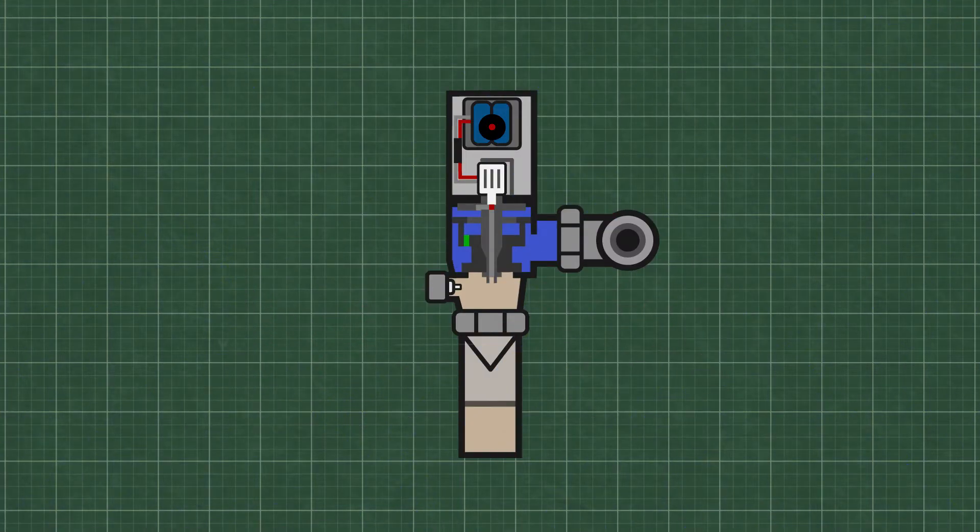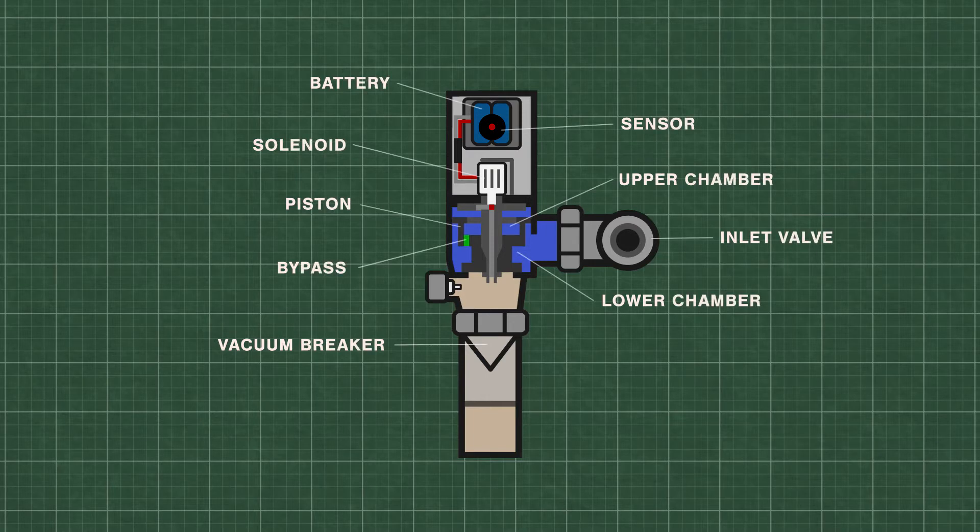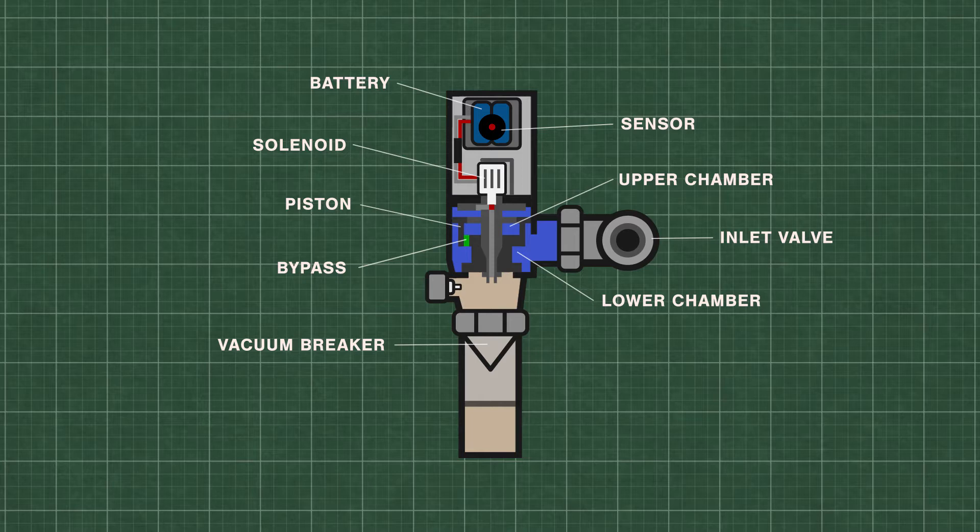Flushometers or flush valves are just automatically timed self-closing valves. At rest, water is at equal pressure in the upper and lower chambers. This keeps the piston closed tightly on the valve seat.